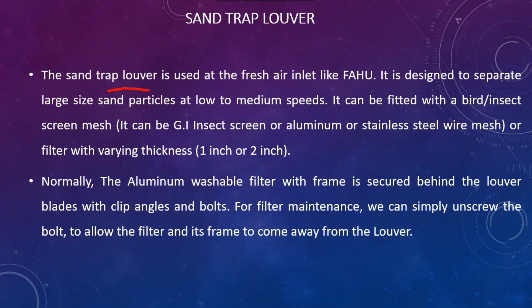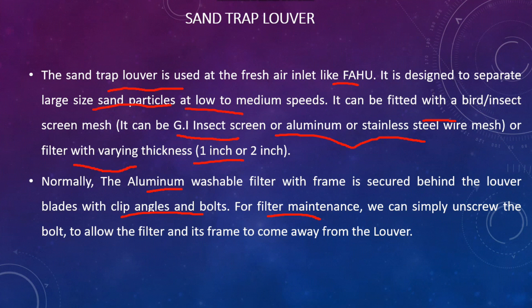The sand trap louver is used at the fresh air inlet, like an FAHU. It is designed to separate large-size sand particles at low to medium speed. It can be fitted with a bird/insect screen mesh — either G.I insect screen, aluminum, or stainless steel wire mesh or filter — with varying thickness like 1 inch or 2 inch. Normally, the aluminum washable filter with the frame is secured behind the louver blades with a clip angle and bolt. For filter maintenance, you can simply unscrew the bolt to allow the filters and frame to come away from the louver.